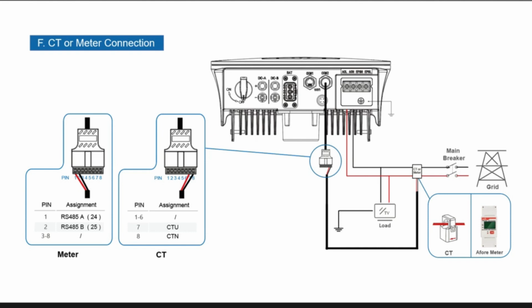Yes, you could put that then on one battery, which then gives you the voltage that you actually require, and then tandem up the second 3-phase inverter, which would then lift the base load of the property up, so you would need to be using less of the battery power from it. I do understand that, but I won't be able to charge the battery. These inverters are one battery, right? Yes, you will be able to charge. You won't be able to charge the other battery directly from it, but because you've got a master and a slave, wow, this is a good question.